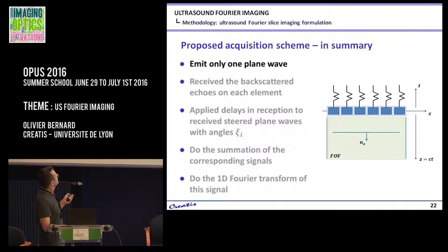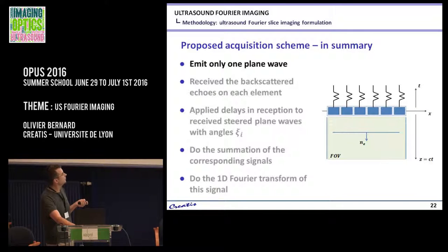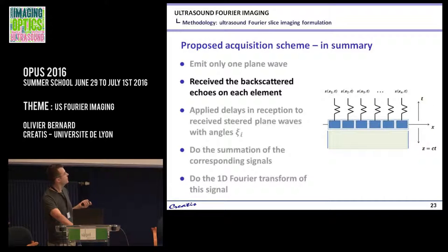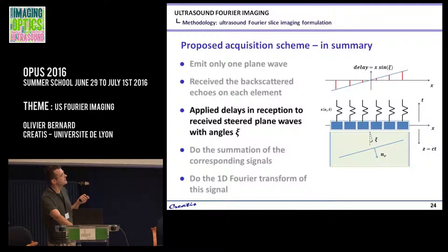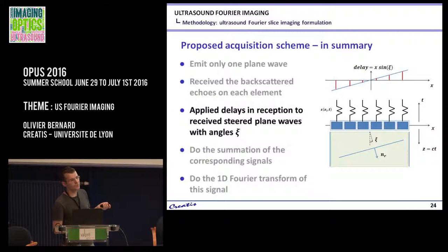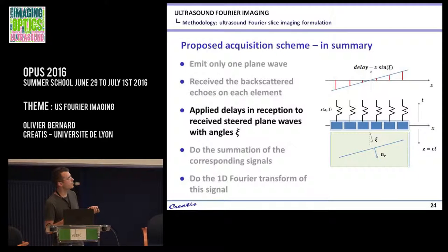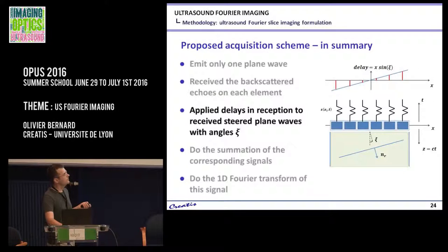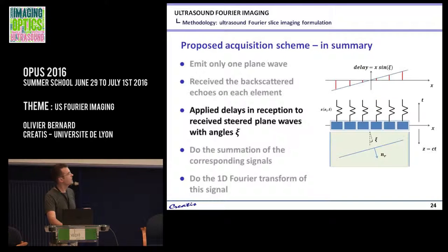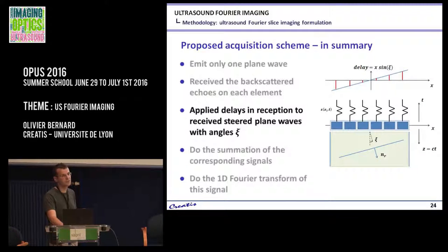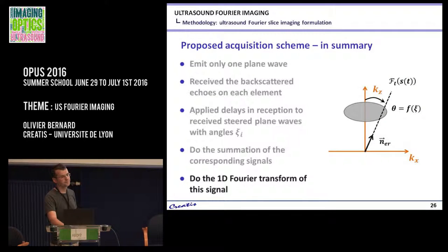If you are able to emit one plane wave, first you emit it and receive your signal. Then you apply delays on the received signal to receive like a steered plane wave with a given angle — this angle is linked to the delay applied. To be faster, we do everything in the Fourier domain, where the delay corresponds to multiplication by a complex exponential. Then you do the summation of the delayed signals, do the 1D Fourier transform, and you have one line in your Fourier spectrum. You repeat that with different delays in reception to densely recover your Fourier spectrum.